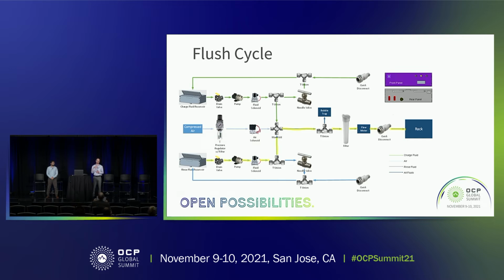And what this does would then push that fluid through to the manifold and then ultimately through a bubble trap to ensure there's no air within the fluid that you're pushing into your rack, and then through a filter so that there's no contaminants, and also a flow meter, so the operator knows the speed at which the fluid is entering your rack or your liquid-cooled system. One thing I intentionally left out here, I'm not showing where the fluid leaves the rack.